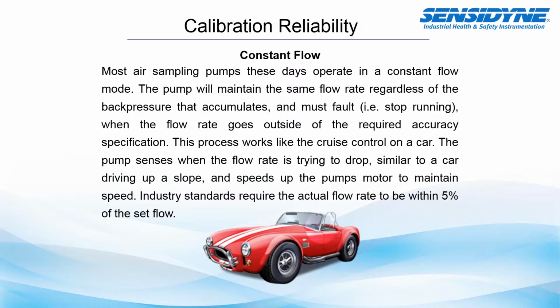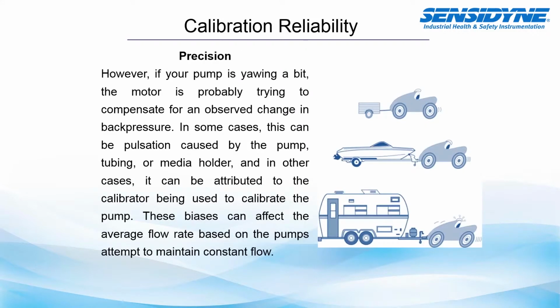Now, industry standards require the actual flow rate to be within 5% of the set flow rate, which means when you do your pre-calibration and you set your desired flow rate, your post-calibration should be within 5% of that set flow rate when you started. Now, if your pump is yawing a bit, which means it'll rev and you'll kind of hear the pump trying to accommodate for a noticeable change in pressure, it'll start revving. This means the motor is probably trying to compensate for an observed change in back pressure.